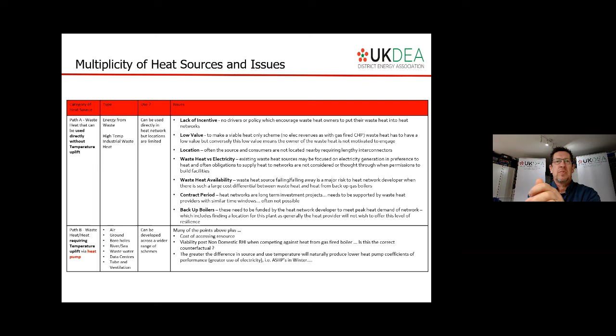So to summarise: are heat networks viable in the third age? I think high temperature waste heat, with commercials that work, say a penny to a penny and a half per kilowatt hour, is possible. Low temperature waste heat with no renewable heat incentive, and this is a key point, heat charges set against a gas-fired boiler counterfactual, even with a significant capital grant, is not viable. The problem is we've lost the RHI. If you're trying to sell heat under a long-term agreement to develop your heat network and set it against a gas-fired boiler counterfactual, having to put low carbon waste heat in at low temperatures and then into a heat pump, it's very, very hard to make those work.